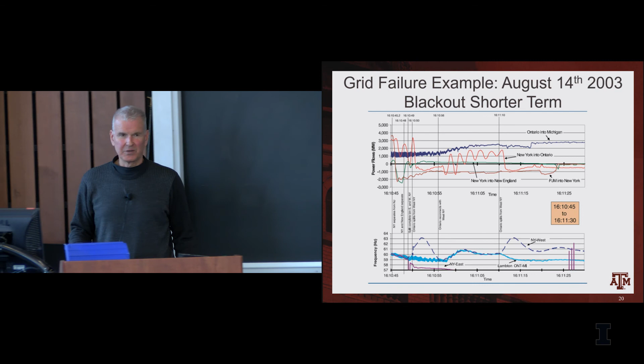This is showing the frequency on the system over the course of those same 30 seconds. The difference here is the scale is much, much larger than the scale on the visualization that I just showed you. In the visualization I just showed you, we went from 60 hertz to about 59.9 hertz. Here the scale is 60 hertz, 61 hertz, 62 hertz, 59, 58. So there was a large disturbance on the grid that day that ultimately resulted in the blackout.